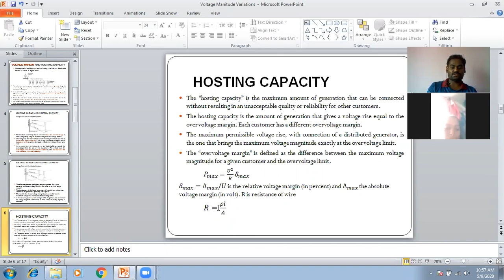The hosting capacity is nothing but the maximum power that can be connected without a problem in a power system. Pmax is nothing but the maximum power from the DG I am going to connect to the power system, right? So this maximum power is proportional to what? The square of the voltage level. So this U is nothing but the voltage level, squared.